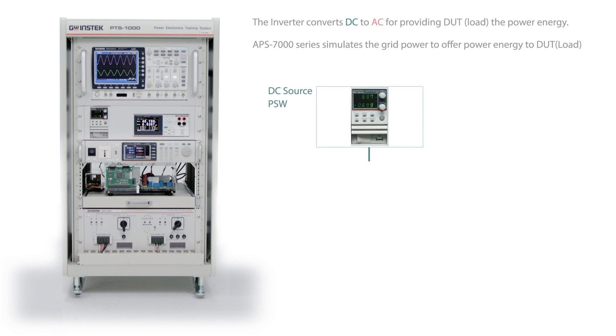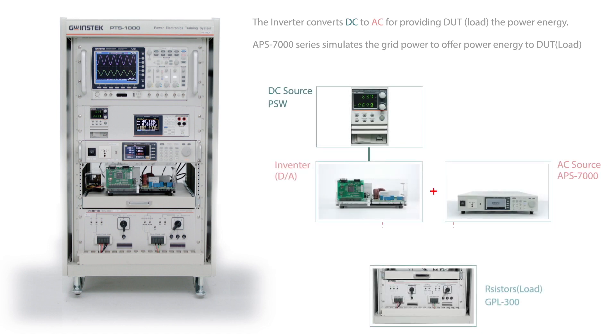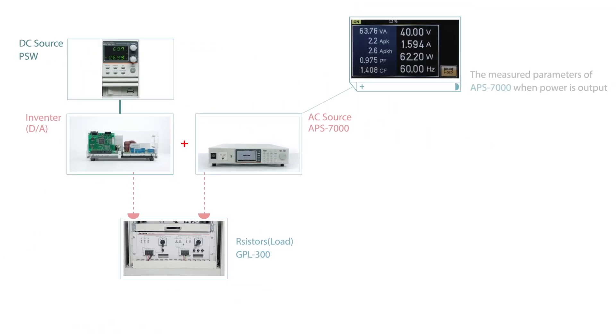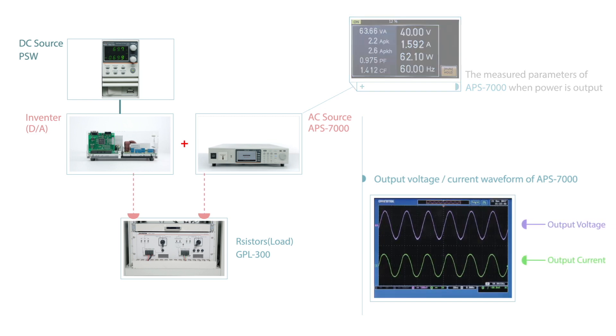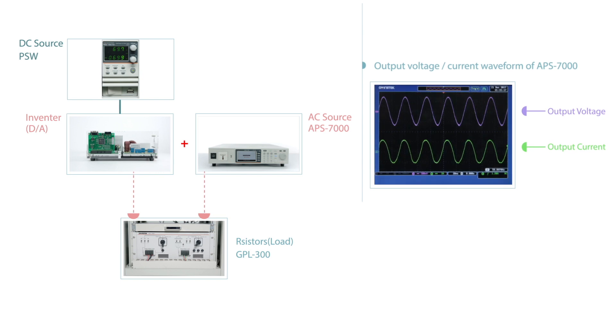The APS-7000 simulates grid power to provide power energy to loads, while a DUT inverter transfers from DC to AC to provide power energy to loads at the same time. This is used to simulate grid power output and allows inverters to do the test of connecting in parallel with the grid power.